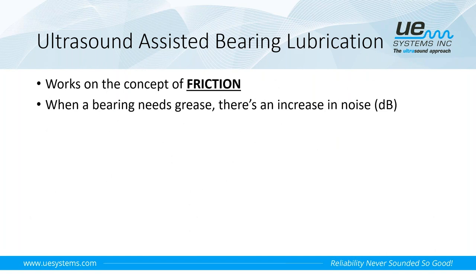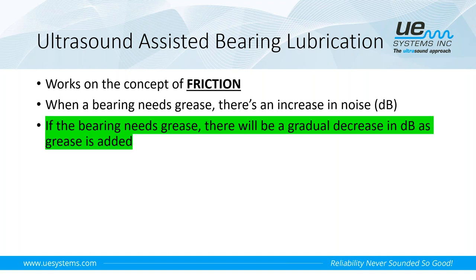So what we can expect to see and then hear when we're out there with our Ultraprobe 401, and again, the Ultraprobe will give us the decibel level once we make contact with that bearing. What we want to see is, if that bearing needs grease, there will be a gradual decrease in dB as grease is added. As grease enters the bearing housing, there's less friction, therefore less noise. And then once it drops, it's not likely to fall anymore. So there's no need to apply more grease after it has fallen to see if the decibel level will continue to fall. At that point, we can stop adding grease.